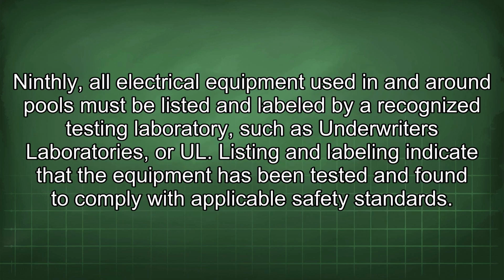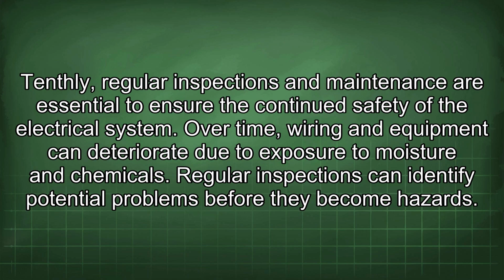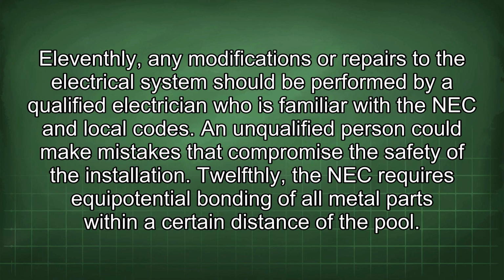Ninthly, all electrical equipment used in and around pools must be listed and labeled by a recognized testing laboratory, such as Underwriters Laboratories, or UL. Listing and labeling indicate that the equipment has been tested and found to comply with applicable safety standards. Tenthly, regular inspections and maintenance are essential to ensure the continued safety of the electrical system. Over time, wiring and equipment can deteriorate due to exposure to moisture and chemicals. Regular inspections can identify potential problems before they become hazards. 11thly, any modifications or repairs to the electrical system should be performed by a qualified electrician who is familiar with the NEC and local codes. An unqualified person could make mistakes that compromise the safety of the installation.